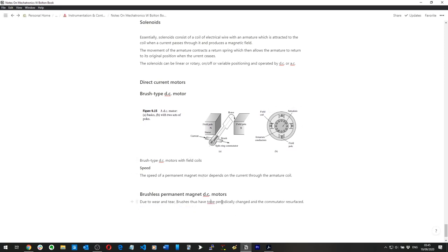Brush-type DC motors require a commutator and brushes in order to periodically reverse the current for each armature coil. The brushes make sliding contacts with the commutator, and as a consequence sparks jump between the two and they suffer wear. Brushes have to be periodically changed and the commutator resurfaced.